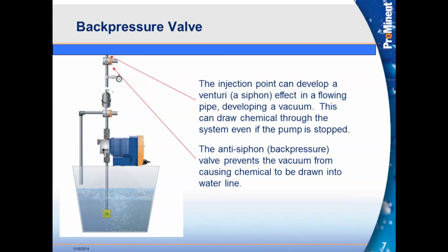And that siphon can actually be created if we have pressure in that line, if we consider that blue line our process flow at the top. If we have pressure in that line, but there's a significant amount of flow, we have some velocity in there, it can still create a lift. It can actually pull the chemical below, up through the pump, into the process if we don't have that back pressure valve included. So with that back pressure valve, the general rule of thumb is to achieve around 15 psi higher on the discharge than we have on the inlet. And sometimes we have to take those negative pressures into account, such as I just mentioned, that velocity of flow in the line can create a negative pressure.